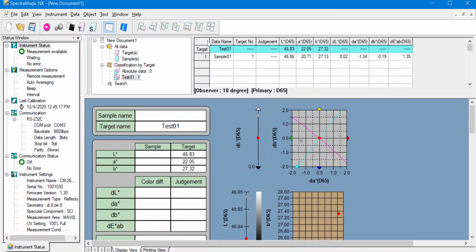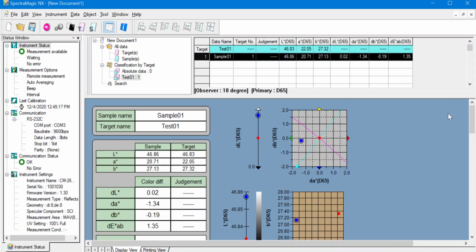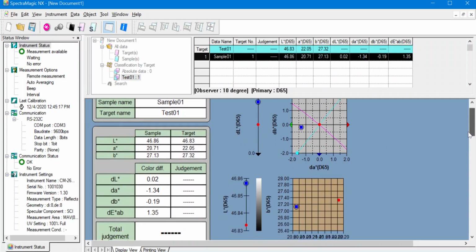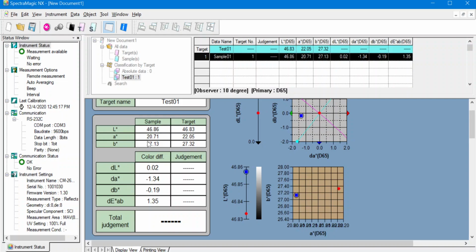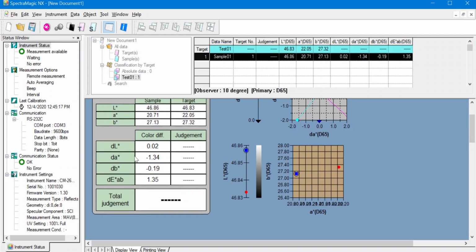Okay. So looking back on the data table, we have again test 01 as the target and sample 01 as the measurement sample. So you can see that sample 01 also records L star, A star and B star data, as well as the comparison between the sample and target using delta L, delta A, delta B and delta E star. So let me select sample 01 over here and you will see that this display has already changed. You have sample 01, target test 01, and it gives you over here the sample's LAB and the target LAB over here. And the color difference is shown over here.